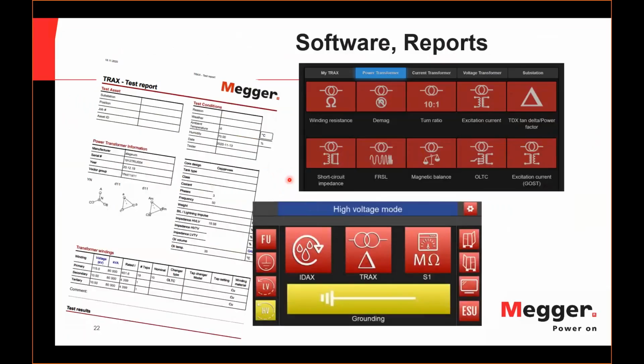Looking at the software, of course, I was telling you that everything has a central control, so you can activate a certain equipment directly from the main computer. For example, you activate IDAX, mega ohm meter, or multifunction instrument TRAX. And at the next step, you move to its own software that guides the testing, collects all the data into a report, and that report is ready to be copied into the overall database or exported to a different ERP system software or any Excel spreadsheet that can be used in external analysis.